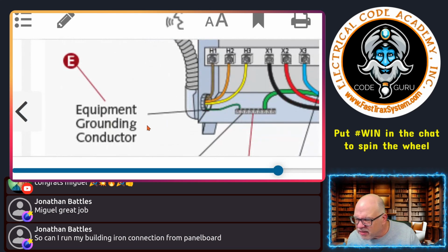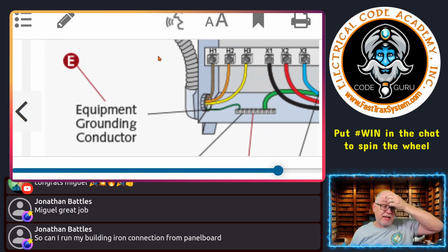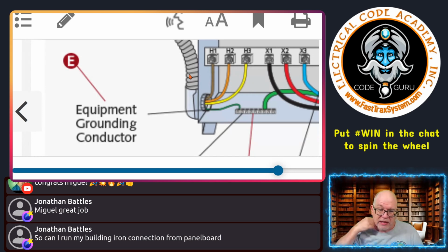Kinda. Okay, so this is the equipment grounding conductor here. It's actually running, they don't show it real well, it's not running to a lug. It came from the primary side, because obviously this armor is too large. The sizing is large. It would not be allowed to be part of the equipment grounding conductor path or effective ground fault current path. So it's bonded.